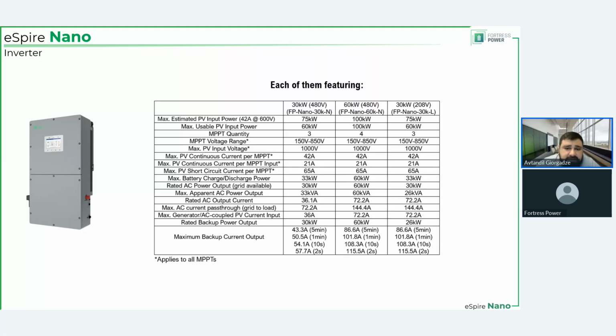MPPT voltage range is the voltage range in which the inverter actually performs maximum power point tracking. Short circuit currents are also given here, 65 amps. Battery charge and discharge currents, as I said, DC side is identical between the 30 kilowatt inverters. Both of them can do 33 kilowatts of battery charge and discharge. Where they differ, though, is on the AC side, right?